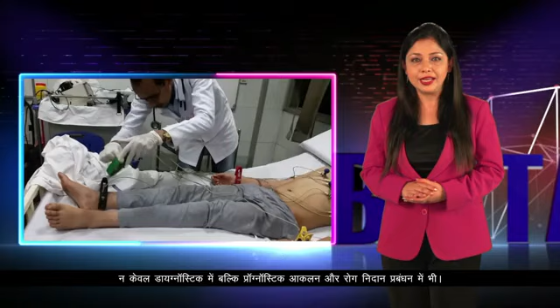Let's hear from Mr. Chandan Kumar about how the BIS standard on electrocardiograph ensures safety and performance of the device. Accuracy of ECG as well as the electrical safety of the electrocardiograph equipment is essential for helping in precise diagnosis and ensuring the safety of the patient undergoing the test. BIS has published Indian Standard IS 13450 Part 2 Section 25, which specifies requirements for basic safety and essential performance of electrocardiograph equipment, associated lead wires and electrodes.